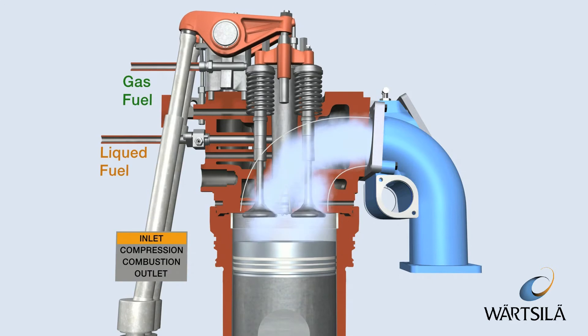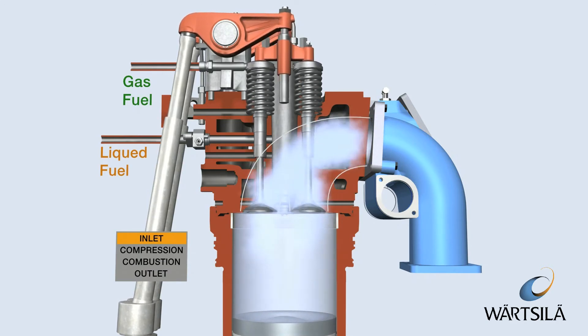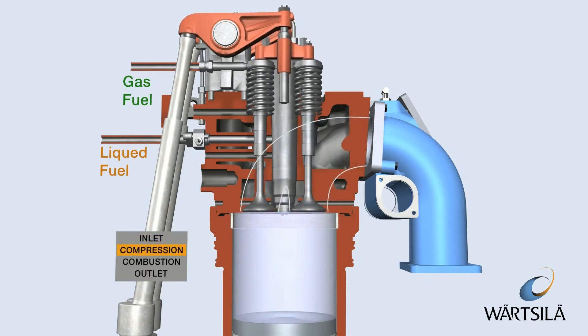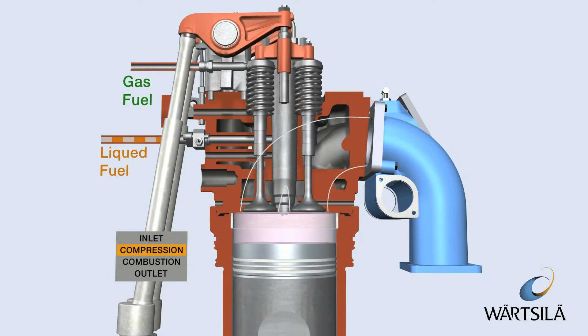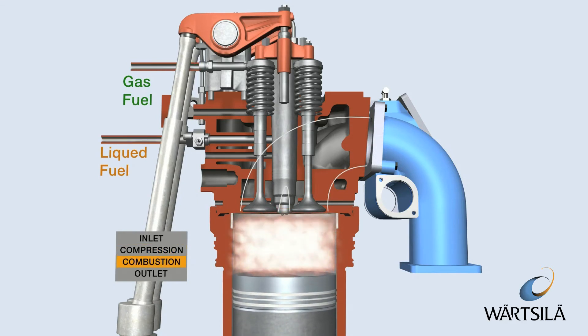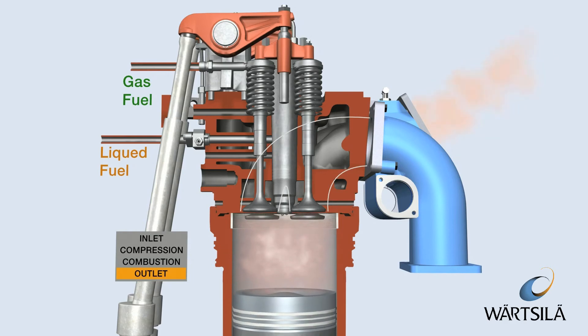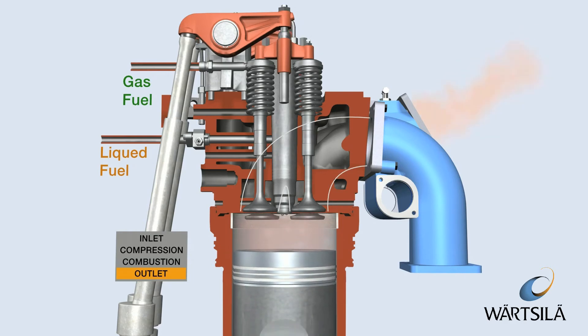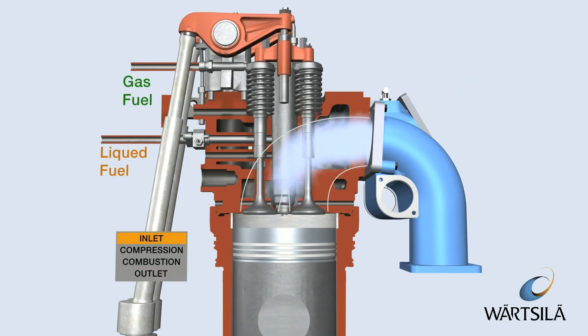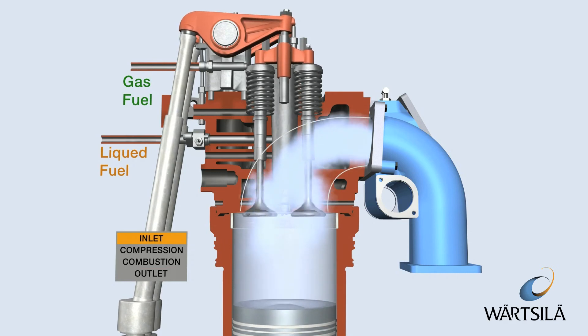In gas mode, the gas is injected at high pressure after the pilot fuel and is ignited by the flame from the pilot fuel injection. The amount of pilot fuel is equivalent to approximately 5% of the fuel energy input at full engine load.